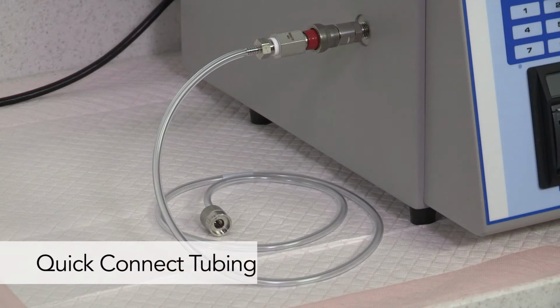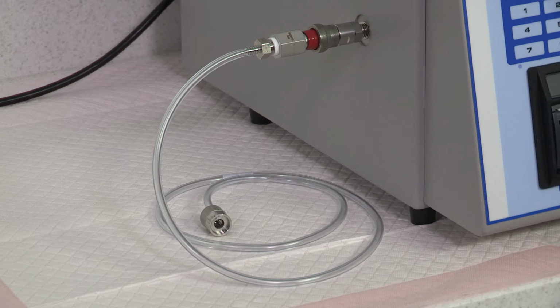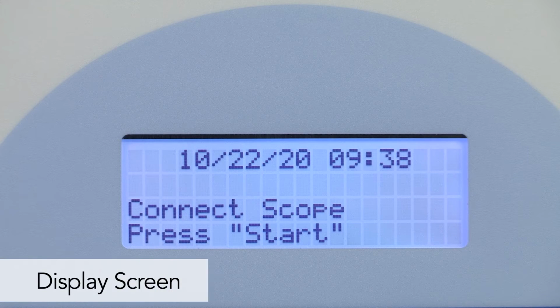The VERISCAN Leak Tester is initially supplied with 1 quick connect tubing. It is recommended that you always have a spare or backup tubing available for each of your specific endoscopes. Additionally, if your facility has endoscopes from different manufacturers, then additional quick connect tubing will be required. The quick connect tubing is not autoclavable and can only be reprocessed using low-temperature decontamination methods, such as wiping with EPA-registered surface disinfectant wipes. The display screen shows important test information and test results.